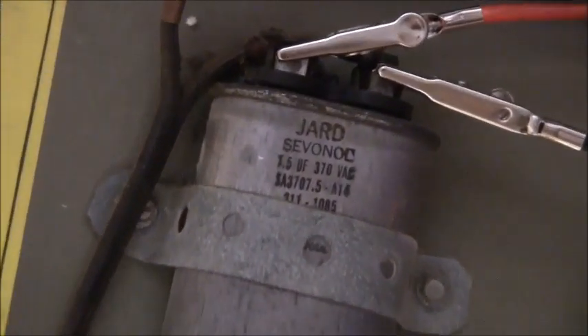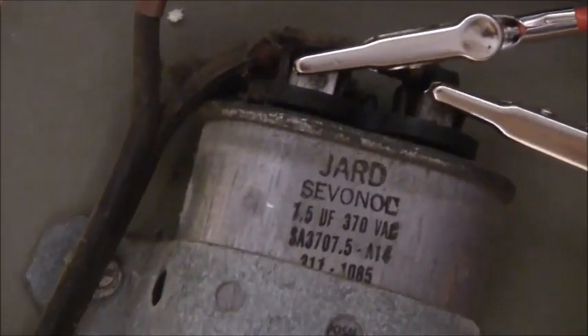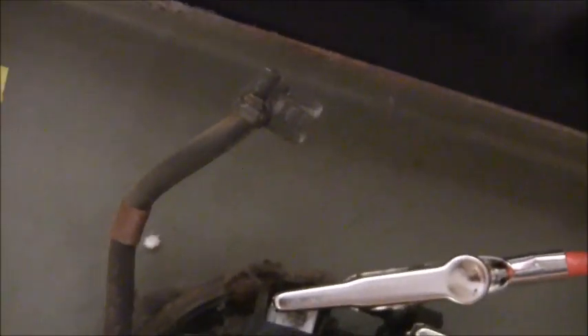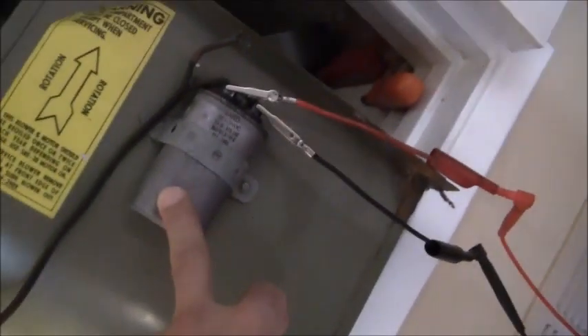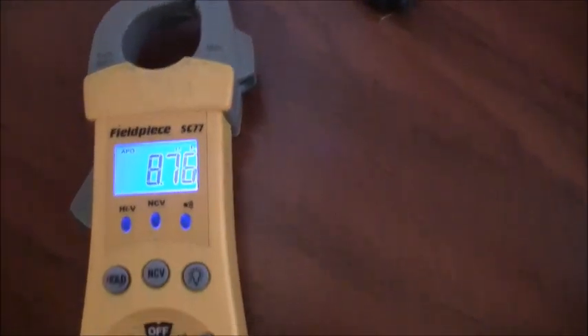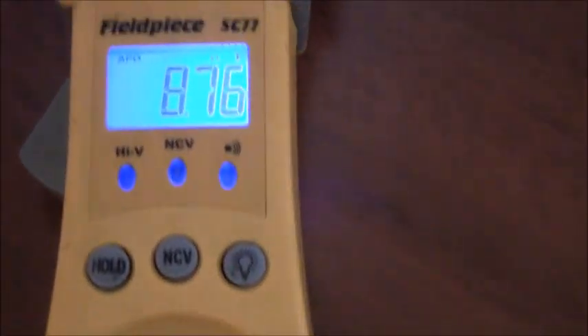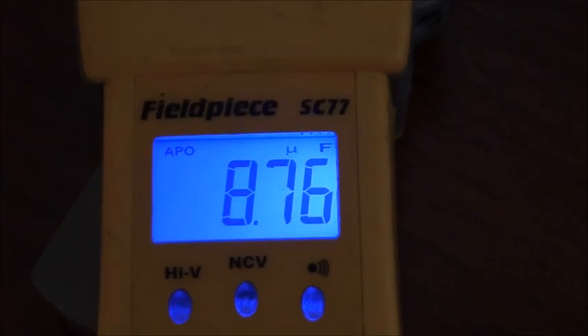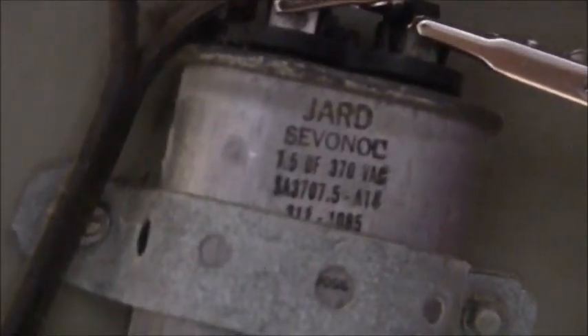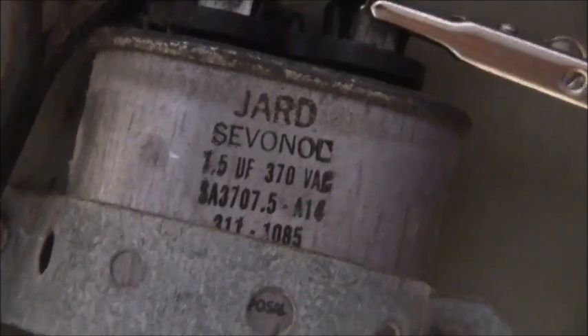The capacitor's already been statically discharged, meaning it's not holding a charge anymore. This capacitor is rated at 7.5 microfarads, and I pulled one of the leads after making sure it was discharged. The electricity is off to the unit, so I'm totally safe. Then I took my Fieldpiece SC77 and put it on microfarads, and I'm getting 8.76. So technically it's a strong capacitor since it's rated at 7.5 microfarads. This capacitor is fine, it's doing fine.